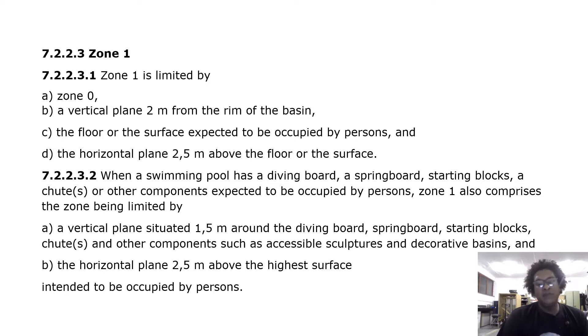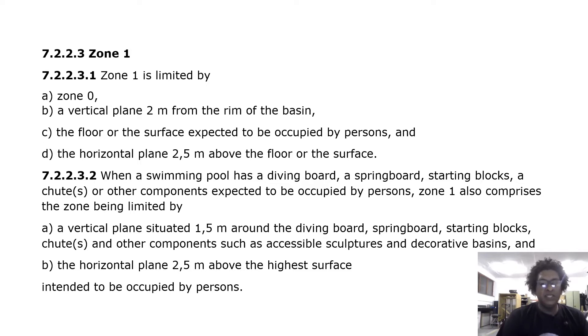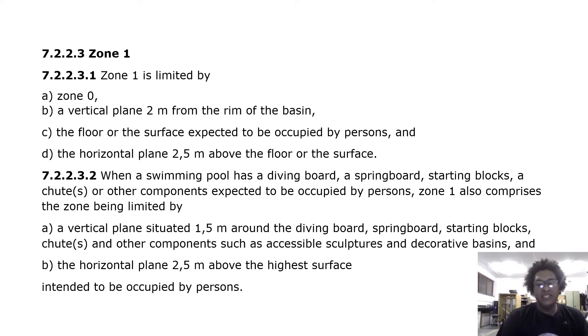When a swimming pool has a diving board, a springboard, starting blocks, a chute(s) or other components expected to be occupied by persons, zone 1 also comprises the zone being limited by a vertical plane situated 1.5 meters around the diving board, springboard, starting blocks and all other such components such as accessible sculptures and decorative basins, and the horizontal plane 2.5 meters above the highest surface intended to be occupied by persons.